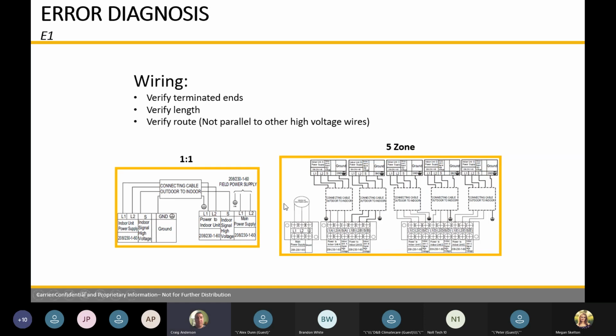So indoor and outdoor unit wiring, we have a single zone and then we have a 5-zone. Like I said, L1, L2, and S need to go to L1, L2, and S. L2 and S are your signal wires, and then L1, L2 are power wires. So L2 is a signal wire as well.